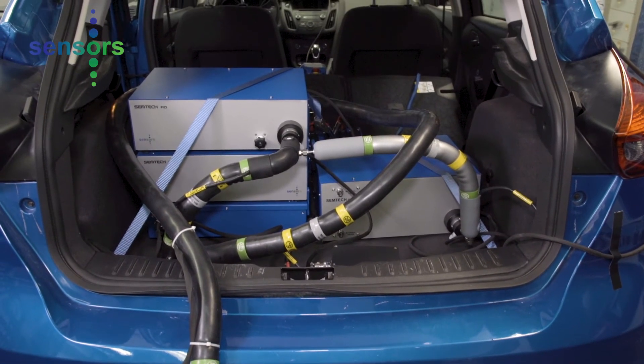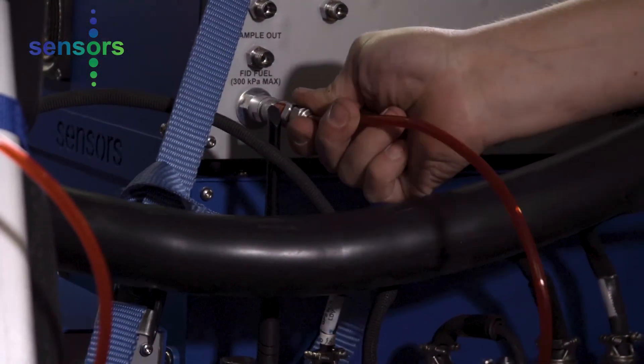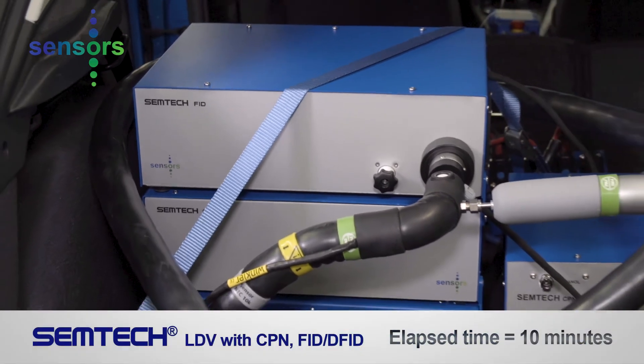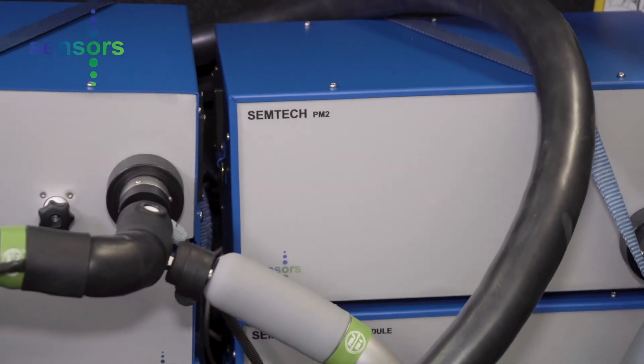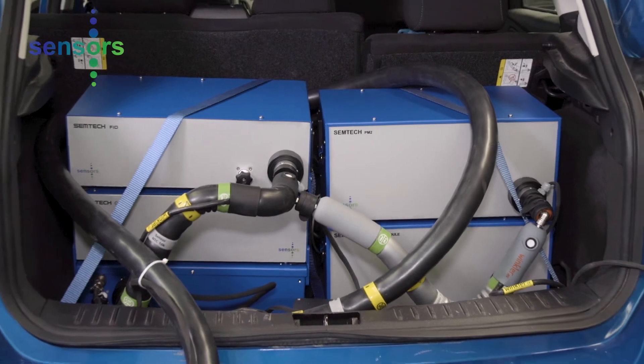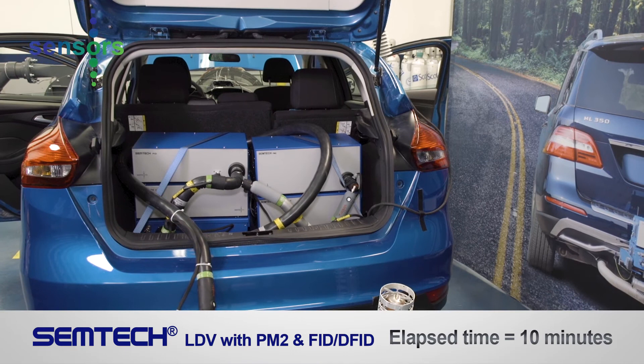Here we added the FID, or flame ionization detector, option to measure total hydrocarbons. A dual FID to simultaneously measure total hydrocarbon and methane is also available. This reconfiguration took our technician an additional 10 minutes to complete. For particulate mass measurement, the CPN module can be removed and a Semtech PM2 module can be connected. The swapping out of these modules took our technician around 10 minutes.